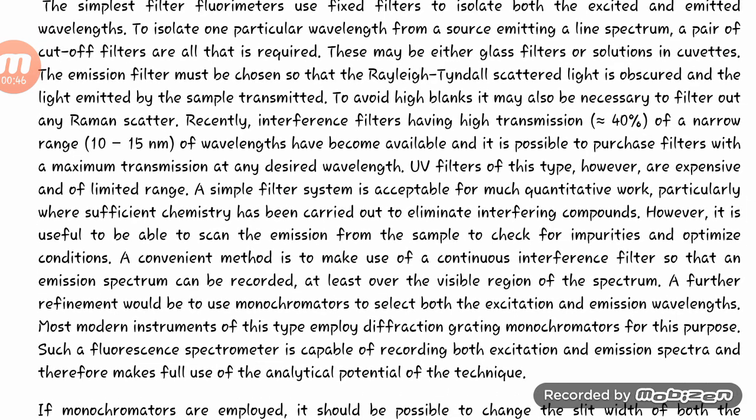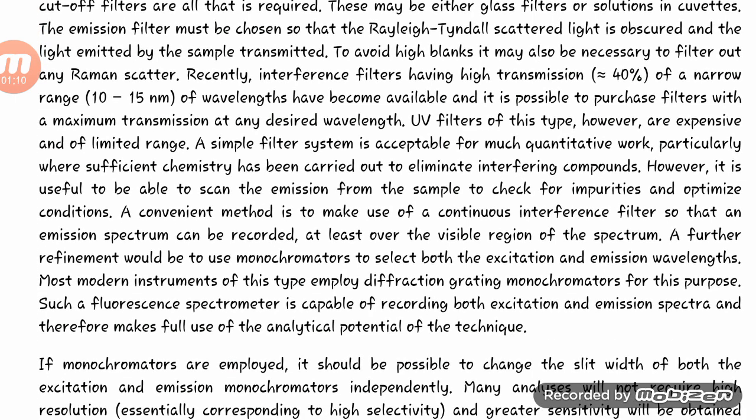The emission filter must be chosen so that the Rayleigh scattered light is obscured and the light emitted from the sample is transmitted. To avoid a high blank, it may also be necessary to filter out any Raman scatter.